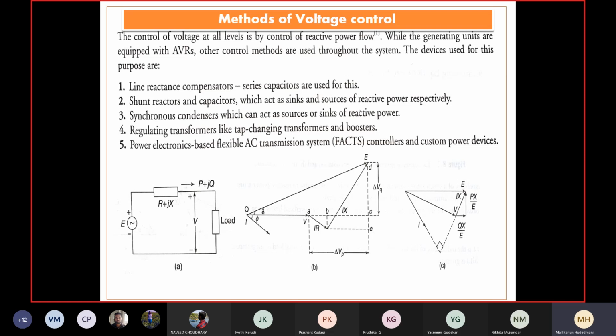The equipments working in the system, based on their terminal voltage, have their plus or minus range of tolerance. Beyond that range, equipments are sure to perform wrongly or malfunction. Suppose they are measuring instruments, those instruments are sure to measure or pick up wrong or erroneous data, which will be used in the computation of your desired control action.